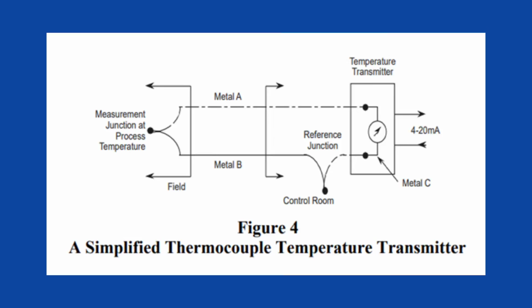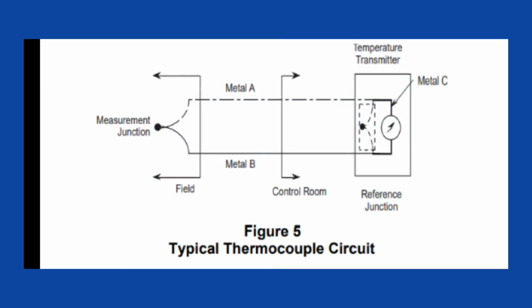In figure 4 above, the temperature measurement circuit consists of the thermocouple connected directly to the temperature transmitter. The hot and cold junction can be located wherever required to measure the temperature difference between the two junctions. In most situations, we need to monitor the temperature rise of equipment to ensure safe operation. Temperature rise is the rise of the device in operation temperature using ambient or room temperature as reference. To accomplish this, the hot junction is located in or on the device and the cold junction at the meter or transmitter, as illustrated in figure 5.